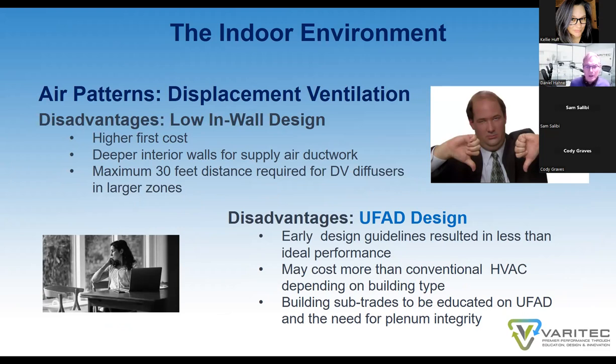Disadvantages of underfloor air is that early design guidelines for underfloor air systems offered less than ideal performance. There were some very compromised buildings with the first edition of ASHRAE's underfloor air design guideline. It was pulled from the shelf in 2012. ASHRAE came out with a revised design guideline in 2015. And I must confess that with the underfloor air systems I've been involved with since then, we have not had the challenges that were experienced with earlier designs.